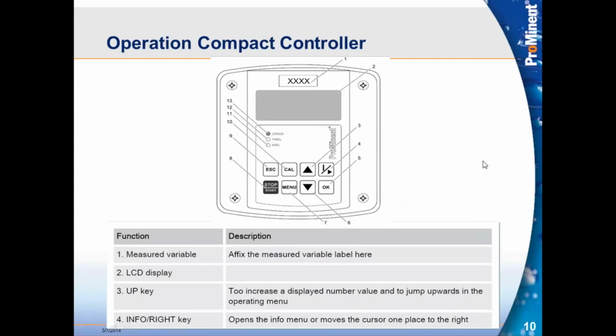What you see on the face of the compact controller, at the top, you're going to see what parameter we've selected at either pH or ORP, and you get stickers for that when you order it. You can change it. Like I said, in the field, you can change what parameter you want it to be controlling. So you have all of those stickers available. Below that is where the display is. An up arrow, so adjusting parameters, adjusting which menu we're using. That could be the up arrow.